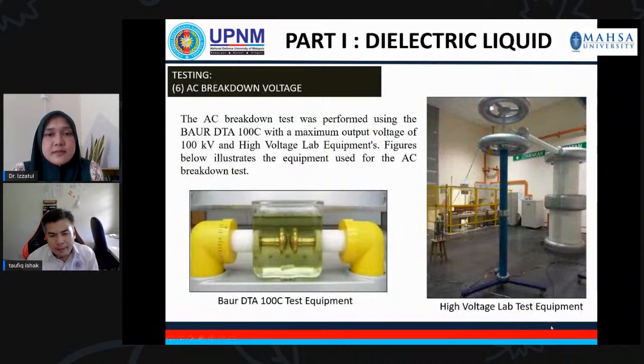All right, so this is a very important test that you must pass before you can sell your oil. This is what we call the AC breakdown voltage, in which we give the AC supply or AC stress to the oil at a certain gap distance. For the standard, normally the gap between two electrodes is around 2.5 mm. In this particular study, we inject the voltage at around 2 kV per step. I mean 2 kV for every step. You increase 2 kV, and if no breakdown occurs, you increase again by 2 kV until the breakdown occurs. Then that particular voltage is what we call the AC breakdown voltage, right?